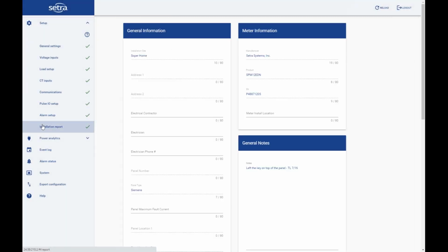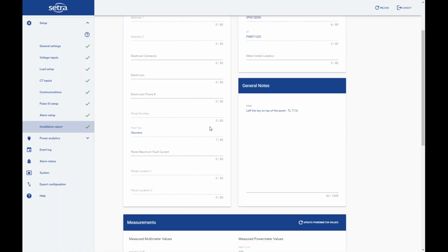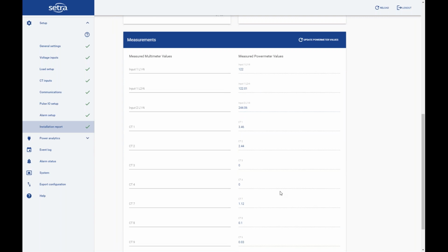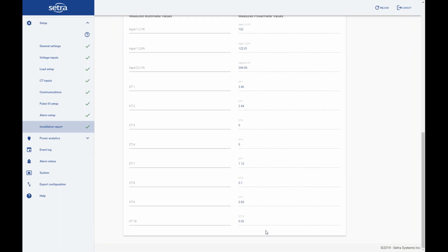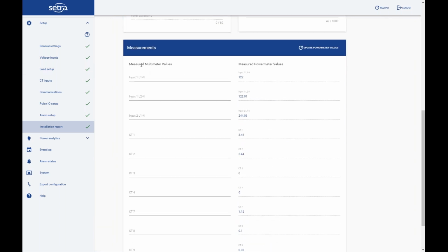The installation report, this is what we mentioned during the presentation, so you can fill out as much of this as you want. You can take a snapshot of the real value that's going on within the meter. And in this column is where you can type in the measured multimeter values. So if you wanted to compare that you actually were seeing 122 or 122.01 or 244 and different amperage at the CT levels, you can save that snapshot so that that'll be kind of proof of your commissioning within there.